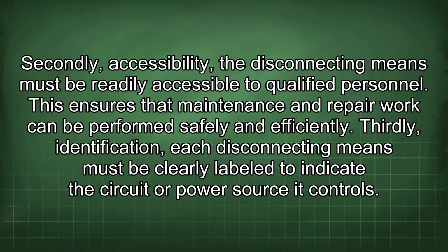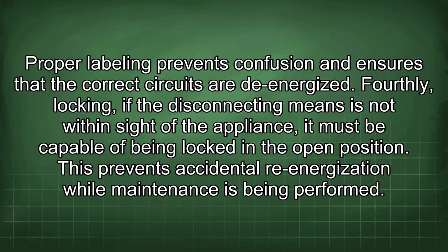Thirdly, identification. Each disconnecting means must be clearly labeled to indicate the circuit or power source it controls. Proper labeling prevents confusion and ensures that the correct circuits are de-energized. Fourthly, locking. If the disconnecting means is not within sight of the appliance, it must be capable of being locked in the open position. This prevents accidental re-energization while maintenance is being performed.